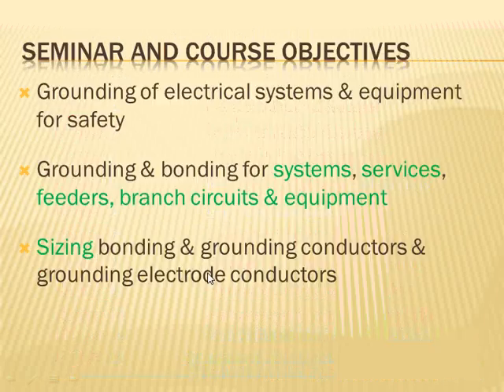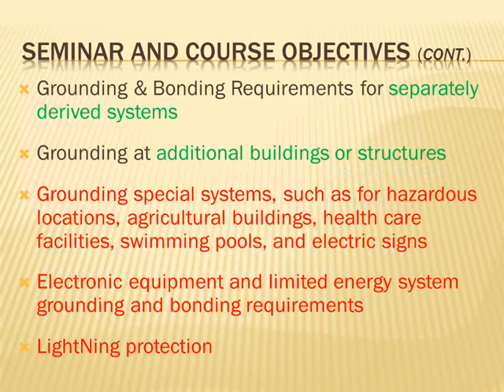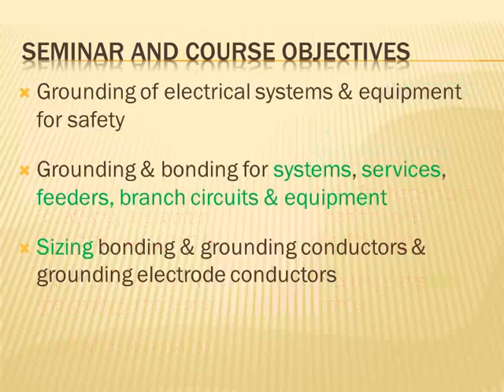Now remember, 95% of the time it's those scenarios I gave to you guys. Now what happens for the 5 to 10% when you don't have to ground the neutral, to ground the system, so the system is ungrounded or it is grounded. So let's talk about these. Let's go back. So, seminar grounding and non-grounding course objective. We'll go over this one. So the only thing, let me go back to these and go over here.